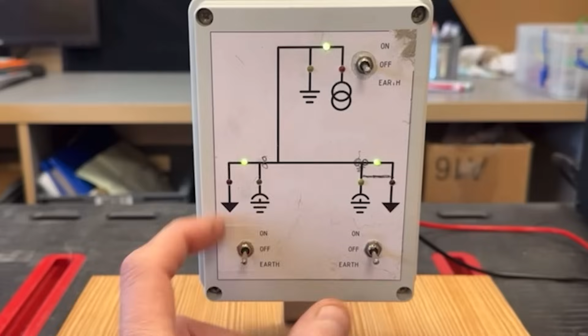What's weird now is I've switched that one on to make that go green because that one's off. But in reality it'd still be on - it wouldn't be live, but it'd still be switched on, which is a weird thing to consider. So the transformer's still switched on and connected to these busbars, but both of these cables are dead.